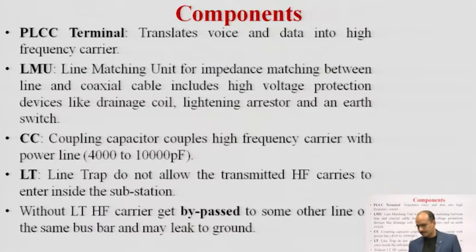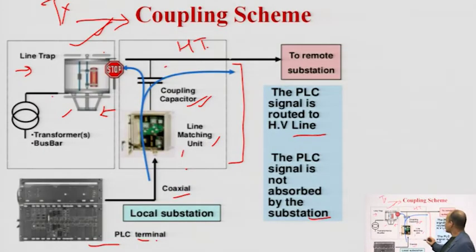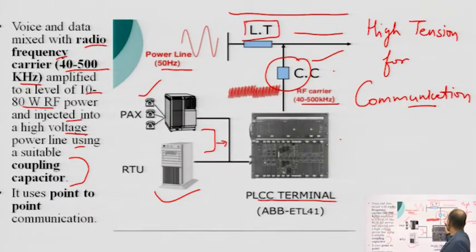Then what are the basic components of this particular part? First of all, there is the PLCC terminal, and that particular PLCC terminal actually translates the voice and data into high frequency carrier, that of 40 to 500 kilohertz. Here you can see that this is the range, 40 to 500 kilohertz.